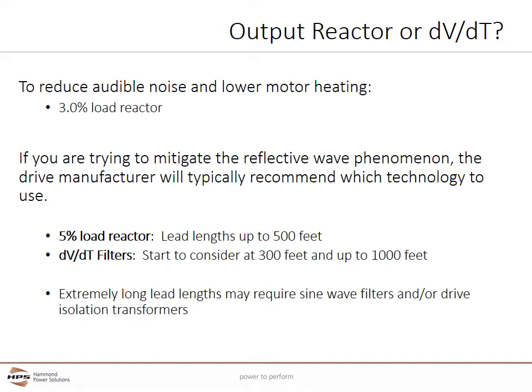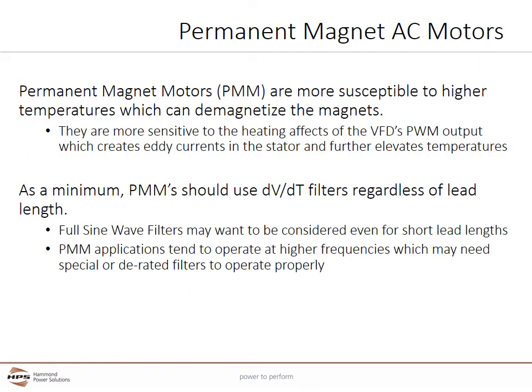DVDT filters combine a load reactor with a filter board containing capacitor and/or resistor components to improve performance over a line reactor alone. DVDT filters are typically considered for lead lengths starting at 300 feet up to at least 1,000 feet. Extremely long lead lengths over 1,000 feet may require sine wave filters and/or drive isolation transformers, which can account for resistive voltage drop in long cables by raising the voltage. Permanent magnet motors or PMMs are more susceptible to high temperatures which can demagnetize them. As a minimum, PMMs should use a DVDT filter regardless of lead length, and full sine wave filters may be considered even for short lead lengths.